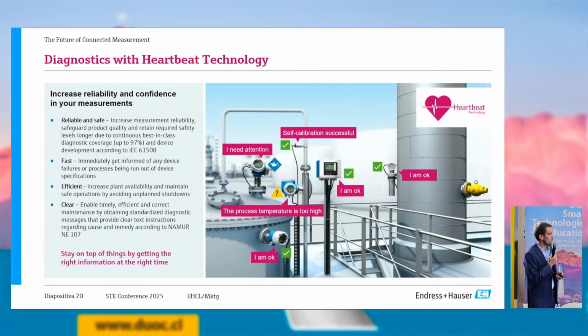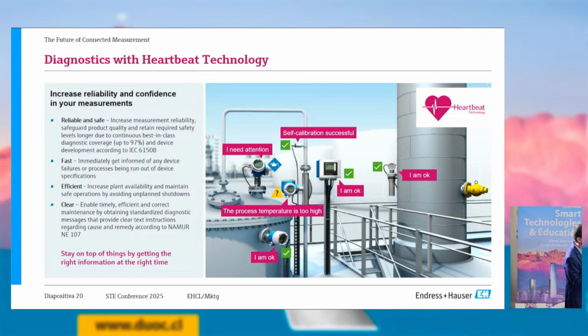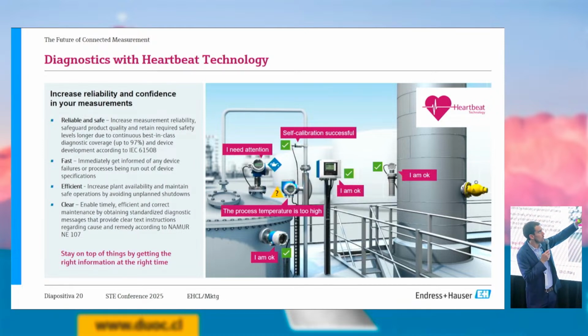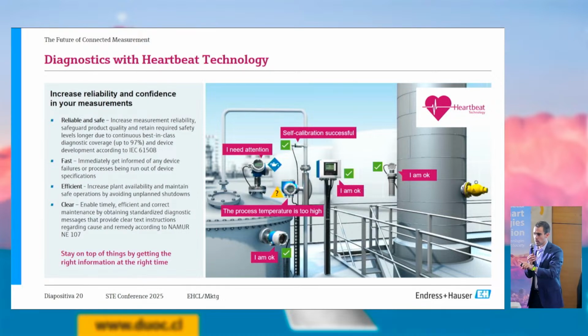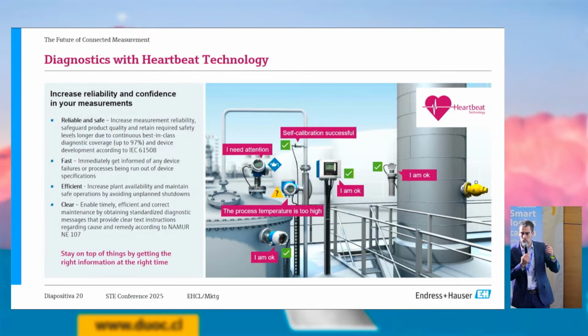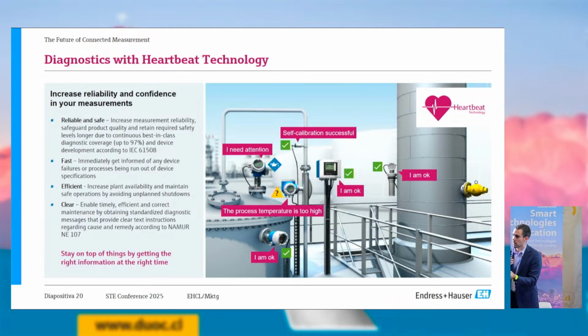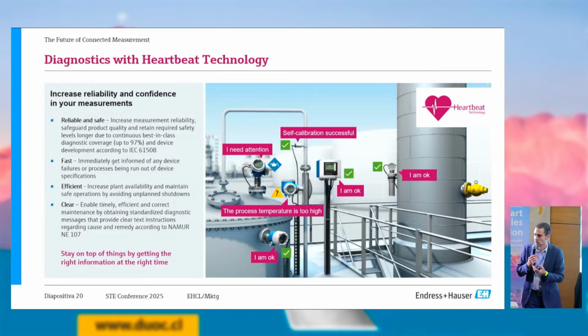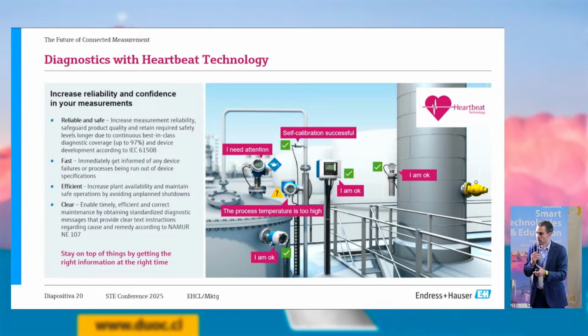From a diagnostic point of view, one device might need attention or maintenance, another might already have a failure—in that case you go either directly to the device connecting via Bluetooth, or to the asset management system, or check the DCS depending on the communication, and you'll see the error behind it, the root cause, and how to fix it. And I don't mean the fix is simply exchanging the device—no. I mean, for example, you have a problem with the communication board, or the same problem with a high frequency module in the case of a radar, whatever it may be.